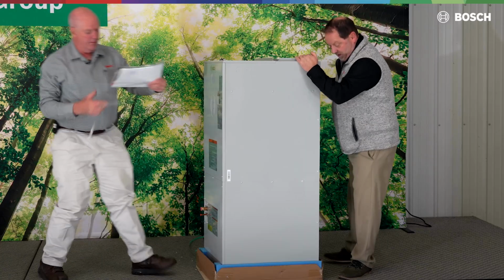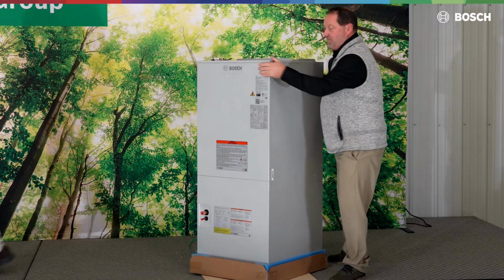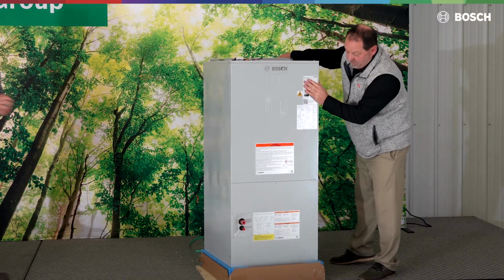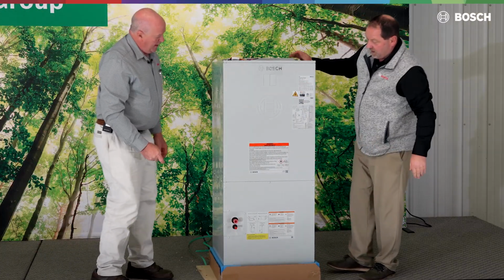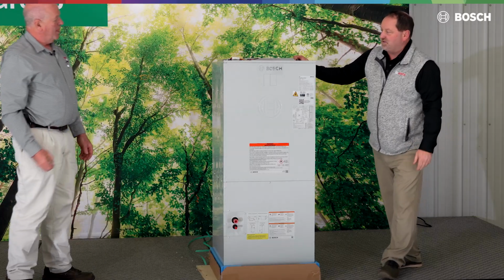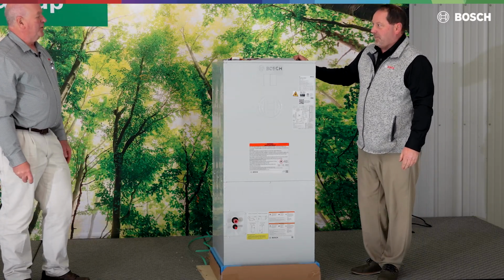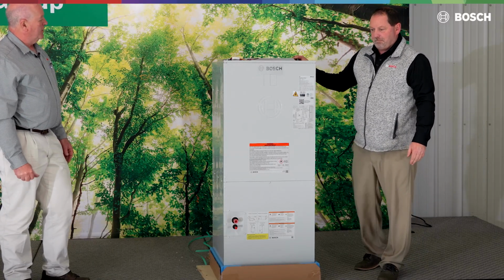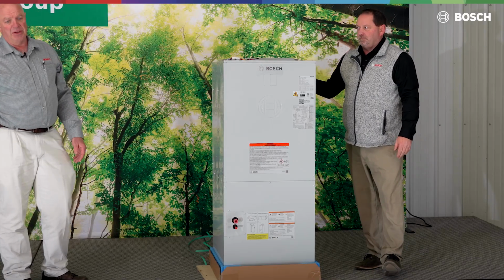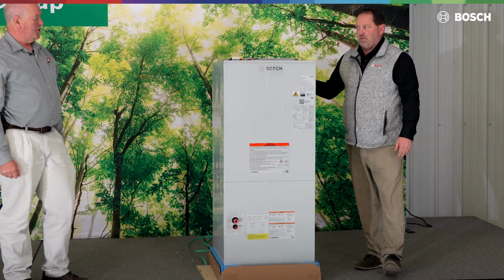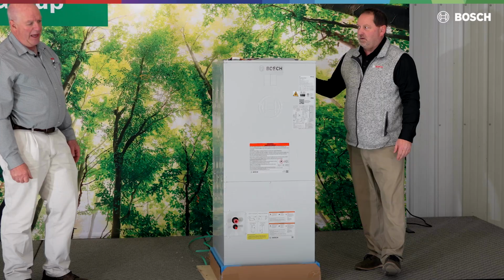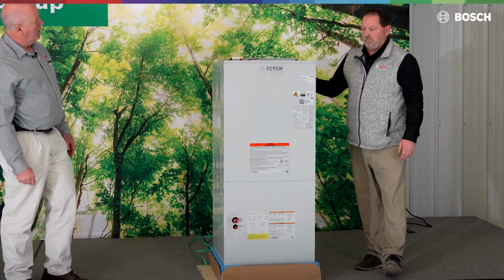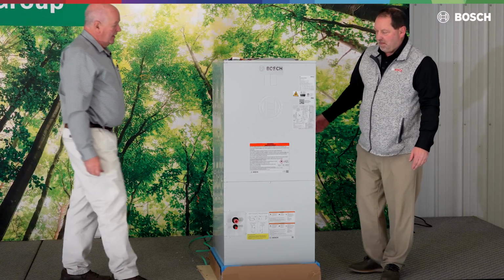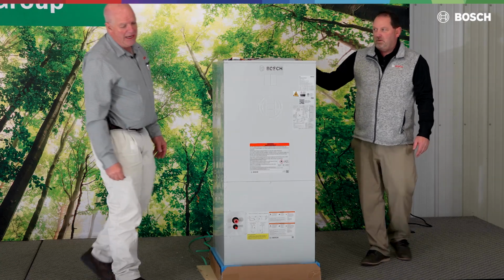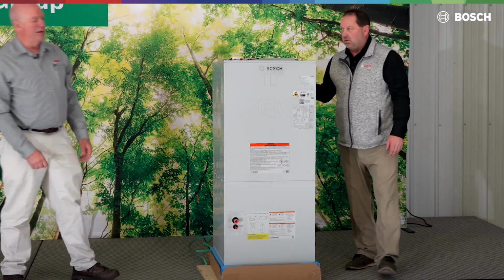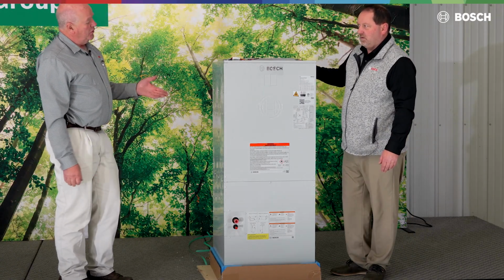So Dave, when you looked at this and said we had the right model, what size did you come up with? This was a 4-ton unit. And why did we choose the 4-ton unit? The biggest thing is for CFM delivery. We have a 4-ton delivery system, 1600 CFM, and we have to fill the duct system to get proper air distribution and static pressure. So we have a 4 and 5-ton air handler available on this size, and the 4-ton fits the need. It also worked out with the BTU loss and heat gain that we did. You have to always do heat loss, BTU, heat gain to make sure that the unit's correct.